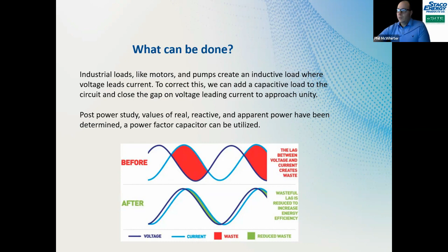All right, so we install a capacitor. What does that capacitor look like? This is a Staco VIR, and 90% of the time, 99% of the time, we're going to recommend a detuned unit because it has detuned capacitors. This helps protect the capacitors from blowing up. We have lots of different options and sizes. We have switched capacitors that will turn on and off based upon your load and your demand. It's microprocessor based, so it's fully automated.